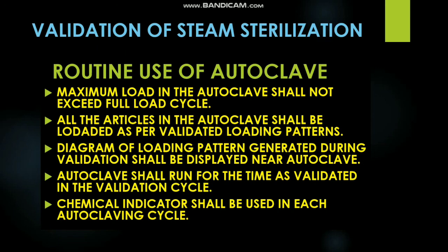All the articles in the autoclave shall be loaded as per the validated loading patterns. The diagram of the loading pattern generated during the validation shall be displayed near the autoclave for ease of operation of the operator or the microbiologist who is doing sterilization. The autoclave shall run for the time as validated in the validation cycle. So if the validation cycle is a 20-minute run, then a 20-minute run shall be executed during routine also. If it is 30 minutes, then it should be run for 30 minutes.